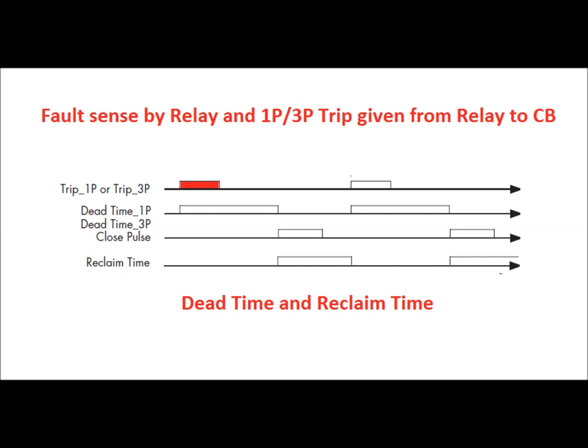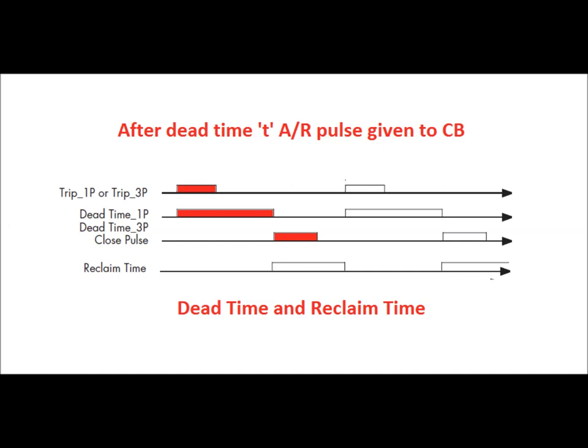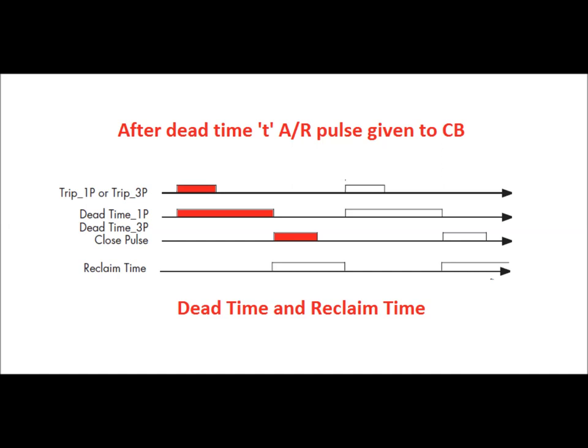Now let us discuss the auto reclose cycle — dead time and reclaim time — using a graphical representation. A single-pole or three-pole trip is issued from the distance relay, shown in red. After the dead time, a close pulse is sent from the distance relay, also shown in red. As soon as the close pulse is given, the reclaim time starts. If any fault is detected by the distance relay during reclaim time, a trip-on-reclose (TOR) is issued. After the reclaim time is over, if a fault is detected, a single-pole or three-pole trip occurs based on the relay settings.